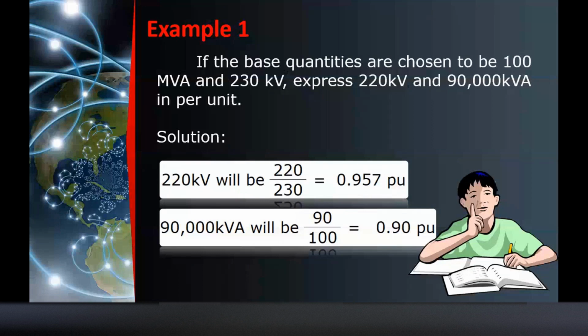So in per unit, we have an example of how to convert. For example, if the base quantities I declared are chosen to be 100 MVA and 230 kV, express the 220 kV and 90,000 kVA in per unit. So simply, the 220 kV will be 220 divided by 230. You have 0.957 per unit. Power system students already know that. 90,000 kVA converted to per unit, we have 90 divided by 100, no? You will get 0.9 per unit. That's okay.